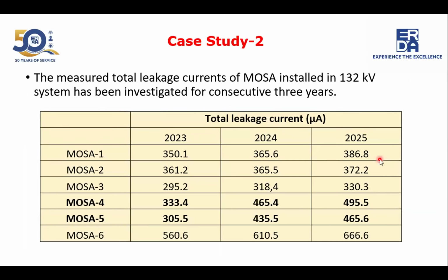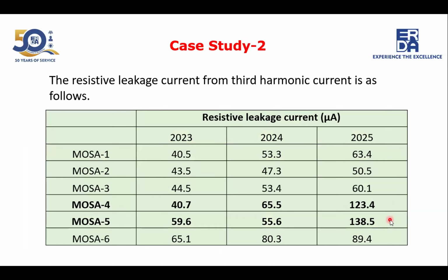This is the second case study, about the 132 kV surge arrestor. Here also 6 surge arresters were studied and analyzed for 3 continuous years, 2023 to 2025. Here we can see MOSA 4 and MOSA 5 showing an increasing trend: from 333 microampere up to nearly 500 microampere, and for MOSA 5, from 300 microampere to 465 microampere in total leakage current.